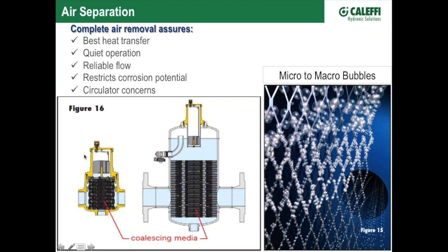One of the keys to making this efficient is having a chamber in here that allows the velocity to slow down as it comes in. It's called a low pressure zone. So the larger you make this area in here, as the flow comes in at, let's say, 4 feet per second, it sees this kind of wide spot in the road. The velocity will slow down for a minute. It gives this media a little bit of extra help to work if we can slow that velocity down and grab that air as it goes through there.